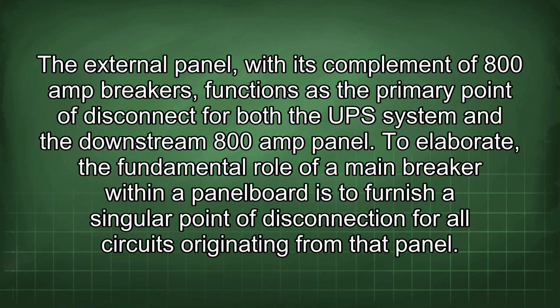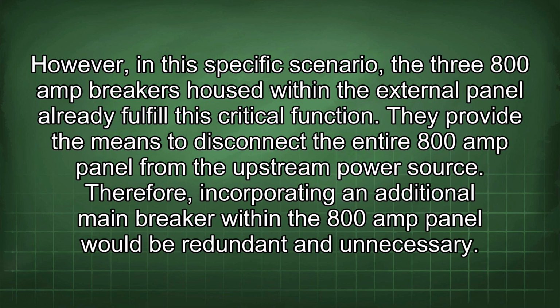The external panel, with its complement of 800 amp breakers, functions as the primary point of disconnect for both the UPS system and the downstream 800 amp panel. To elaborate, the fundamental role of a main breaker within a panel board is to furnish a singular point of disconnection for all circuits originating from that panel. However, in this specific scenario, the 3 800 amp breakers housed within the external panel already fulfill this critical function. They provide the means to disconnect the entire 800 amp panel from the upstream power source. Therefore, incorporating an additional main breaker within the 800 amp panel would be redundant and unnecessary.